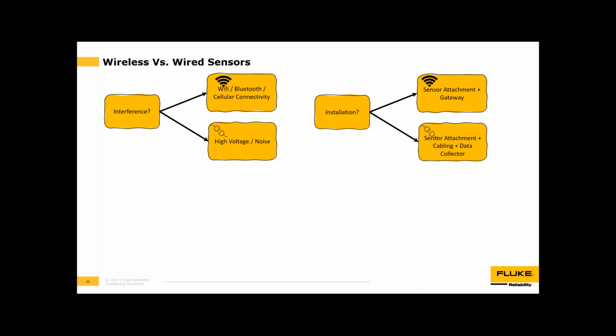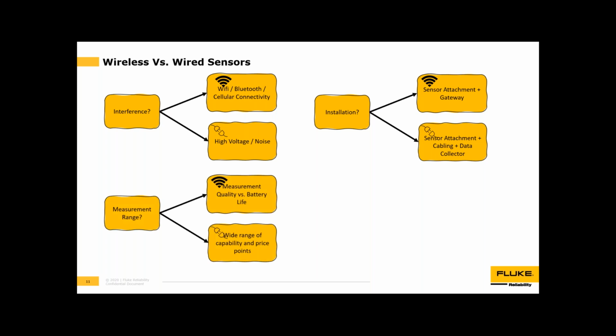With a permanent cable and sensor, there's a little more upfront work—you have to find a place to attach the sensor, which might require the same magnet or physical connections as wireless, but you also have to account for cable runs and where your data collector or system will live. Those considerations need to be made up front to minimize cable runs, maybe using multi-port cables, junction boxes, or conduit for sensors and cable. So there are installation issues that need to be addressed.